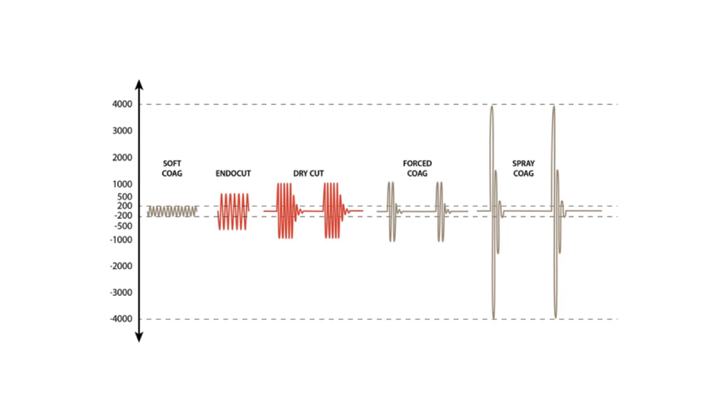When it comes to forced coagulation and spray coagulation, it is a higher voltage with interrupted cycles. Spray coagulation has very high voltage. This is not typically used in snare polypectomy. We use forced coagulation for snare polypectomy and soft coagulation for superficial coagulation and for blood vessel coagulation.